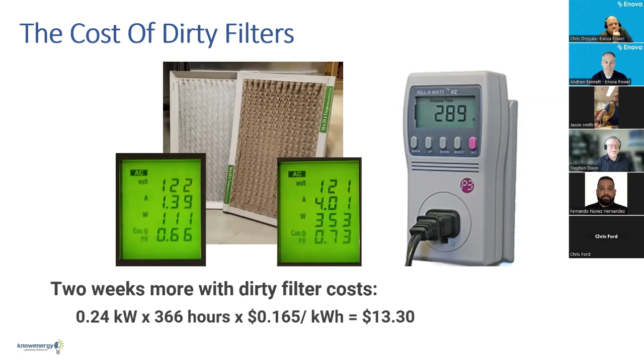How much? The dirty filter, 353 watts. The clean filter, 111 watts. There's the filters, you can see. That's not that dirty, but it is dirty, right? Did the calculation, right? If I'm running that on low speed circulate during the season that I was, if I left that for another 366 hours, that would be $13. Is it worth replacing that filter? Absolutely. But again, that's a fairly efficient system. But because of the fact that I neglected, or someone neglected, to do some basic maintenance on it, it's using a lot more energy. So just because we put more efficient equipment in doesn't mean we're going to get savings. We still have to pay attention to the basics.